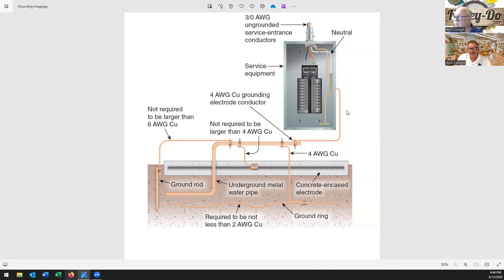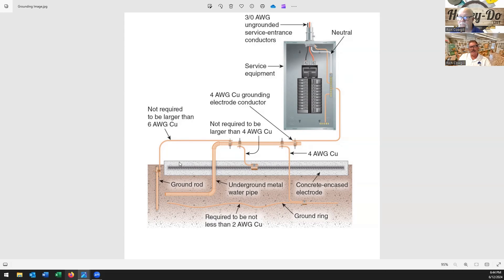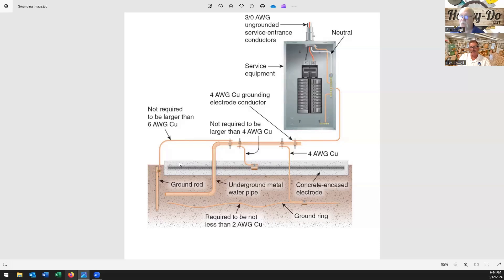So those are interchangeable and that's providing the ground back to the panel. If you don't have Romex, that's why you don't always see a ground in there because the pipe, the EMT, the conduit does that for you. But a good point on that - if you were to remove the outlet from the box and say it's still hot and you plug something in, your outlet may still work but it's no longer grounded because you've removed it from that metal.